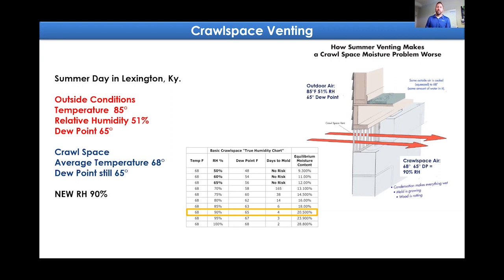If you take a look at this, bringing those outdoor conditions into a 68-degree crawl space, I've quickly taken my humidity up to 90%. The dew point didn't change, but now if I look at that equilibrium moisture content chart in the middle of the screen, it could take just 4 days, if I maintain that same measurement, to start risking mold growth. So this gets back into encapsulation, conditioning, sealing our indoor environment away from the outdoor.